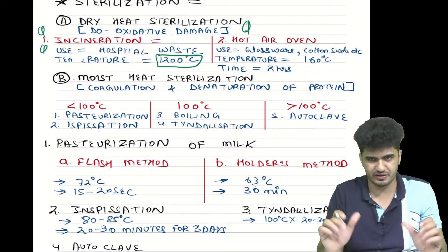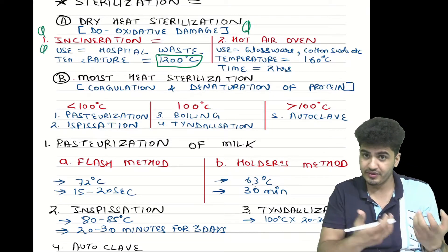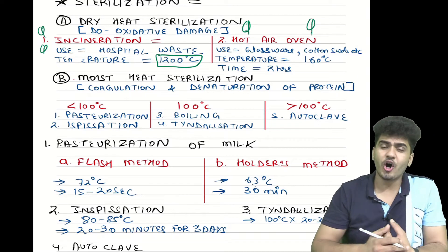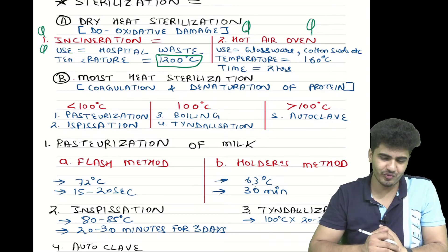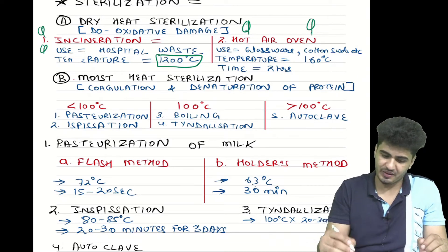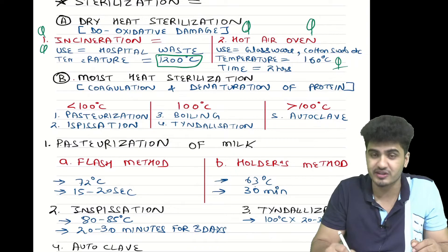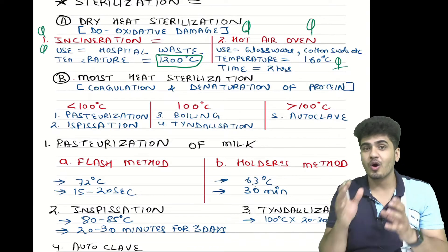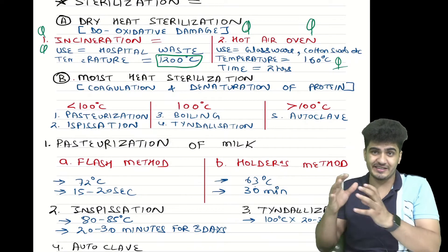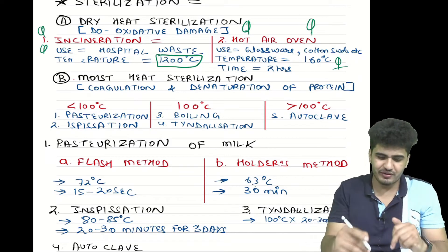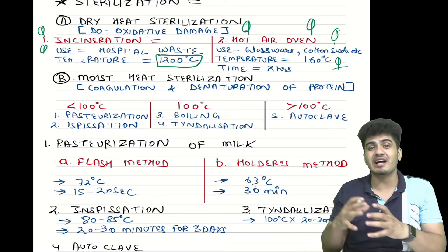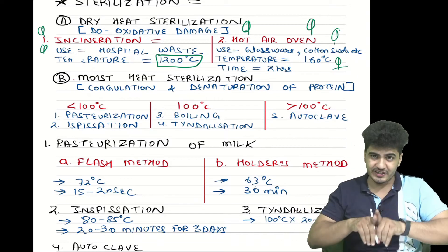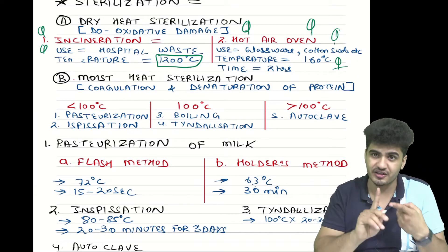The second dry heat method is the hot air oven. Remember, the temperature is 160 degrees Celsius and the timing is two hours — 160 degrees for two hours. It is used for glassware or cotton swabs. So for dry heat sterilization, we have studied two methods: incineration and hot air oven.